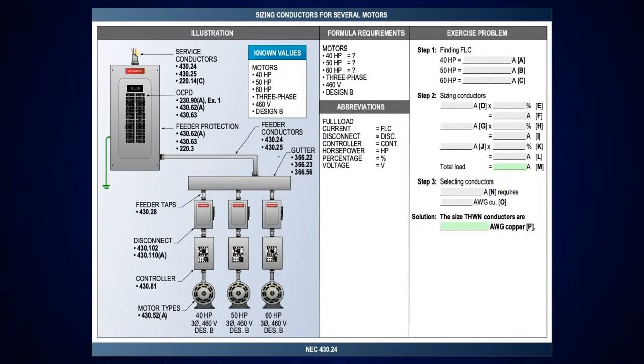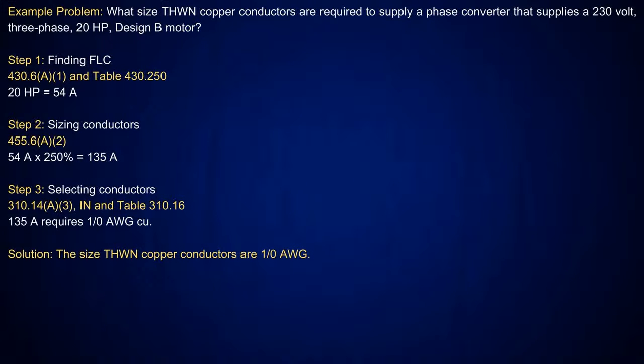Okay? So is there any case where you would have to apply, like if you were under 100 amps, 110.14(C)(1) for that? Well, if the terminals were unknown, you'd go under (C)(1)(b). It gets into the motors, and that's where you've got the 75 C. But you've got to be careful, because if it's an older motor, it could be a 60 C termination, and then you would be using the 60 C column. Would there be anything if the terminals were unknown?